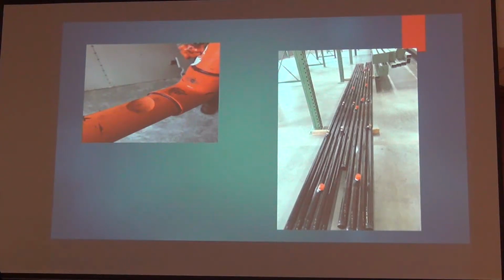Anybody knows what MC is? If you see electricians, that's that metal clad wire that they pull. It's like a flexible conduit. He was using my sprinkler pipe for a pull point. What's the problem? You think it might be a problem? So, he was an apprentice, he learned. Okay, we all learn. So, this is an example of what not to do.